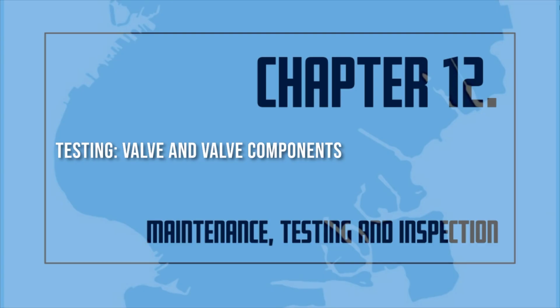Open the inspector's test valve. A burst of air from the device indicates that it has tripped. Close the device's control valve. Return the device to service in accordance with the manufacturer's instructions, and return the system to service.